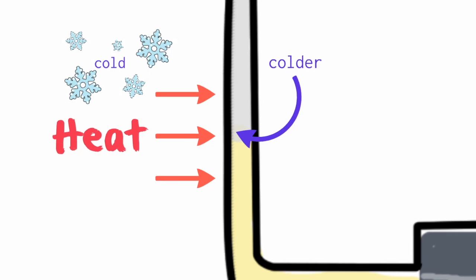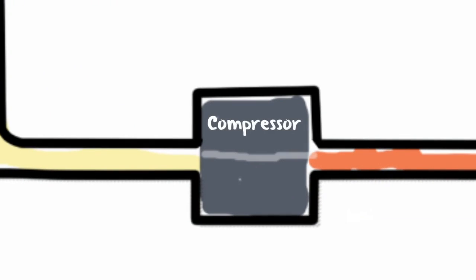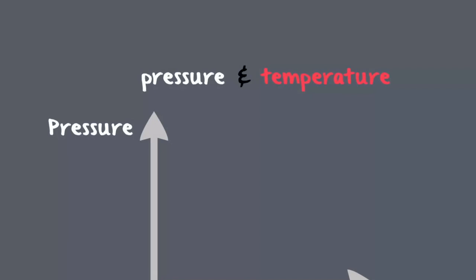This warm refrigerant gas then goes through a compressor that increases its pressure so that it turns into an even hotter gas. This is because there is a relationship between pressure and temperature: as pressure rises, temperature rises.